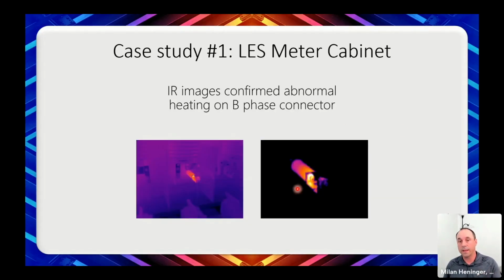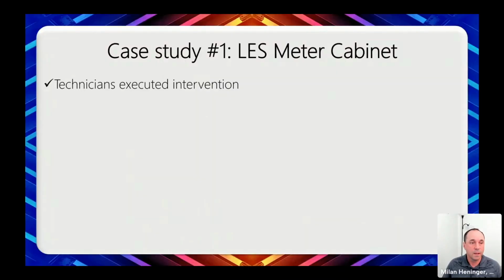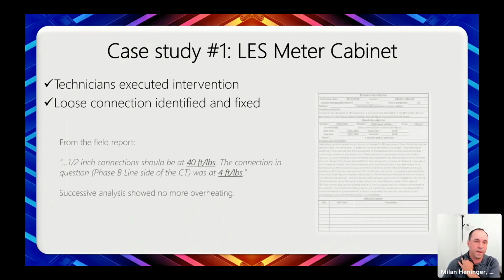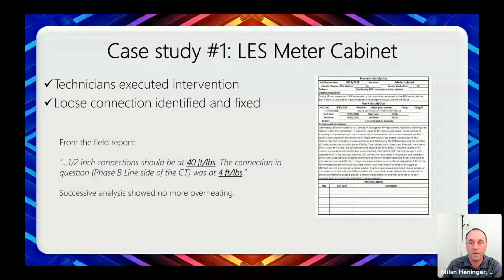We went ahead and did a quick thermography. So they shut the equipment down and opened the doors and shot this image. And you can see that there is some pretty extensive heating on this connector, most likely due to a loose bolt. So our technicians intervened. They identified the loose connection and fixed it. But the interesting thing is that they found that that connection was at about 4 foot-pounds when it should have been, according to the design, 40 foot-pounds. Once we corrected that, there was no more overheating, there was no more arcing or mechanical looseness sounds, and that piece of equipment has been in operation since then. It's been almost 10 years.